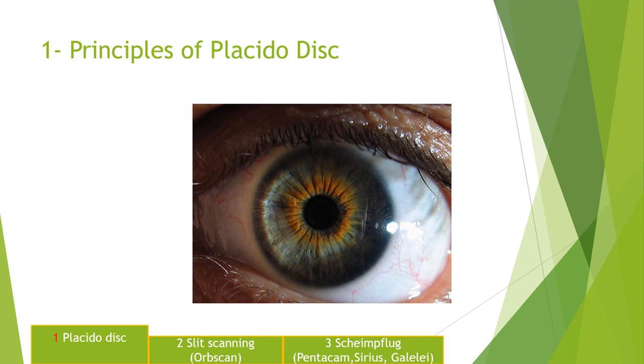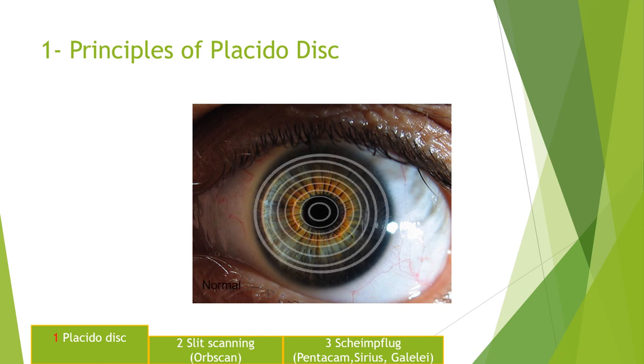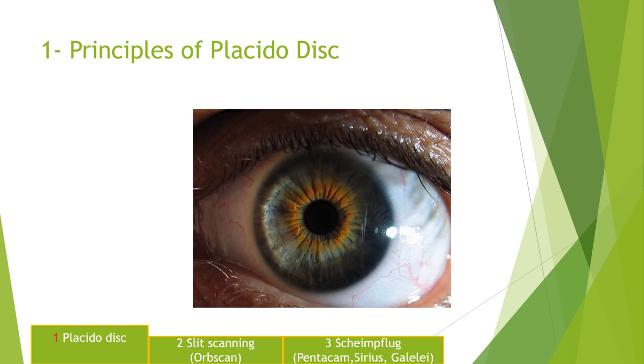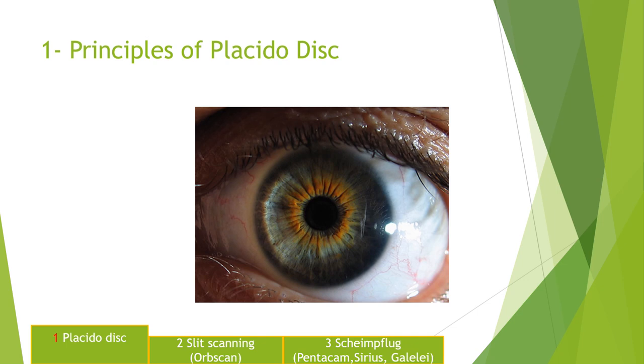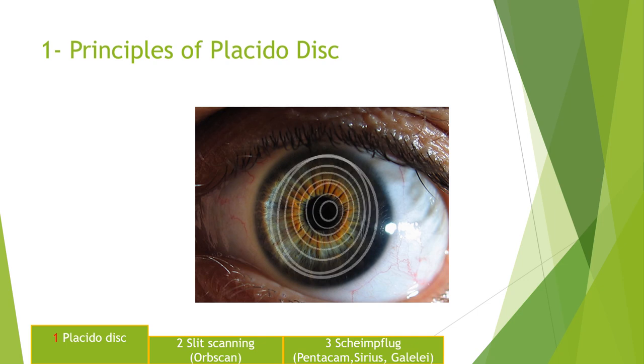This is a cornea where the rings are pretty regular — that is a regular cornea. Another cornea where the rings are regular but oblong in shape — this cornea has got astigmatism. Another cornea where the rings are irregular — this cornea has got an irregular shape. The machine then constructs the topography map and you see the different shapes. This is the principle of the Placido disk: light is reflected from the cornea and the machine makes the topography map, not the tomography map.